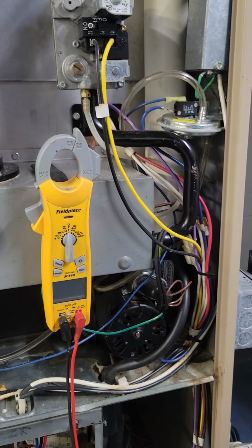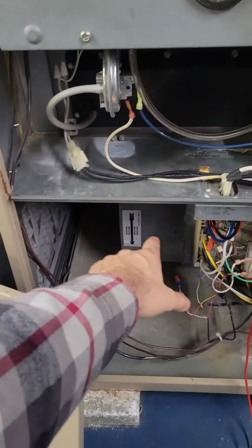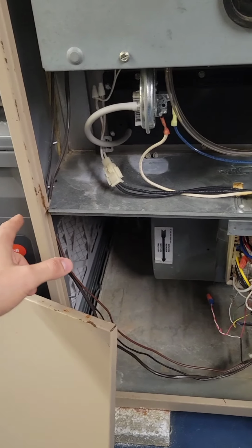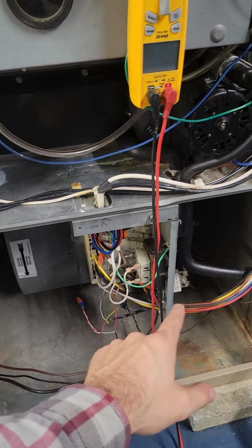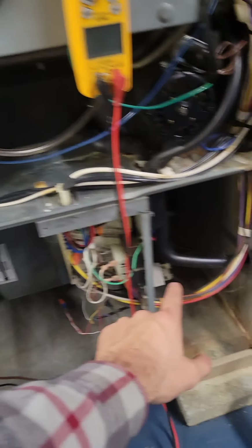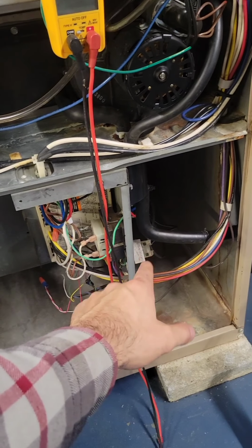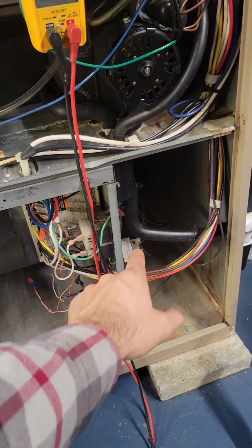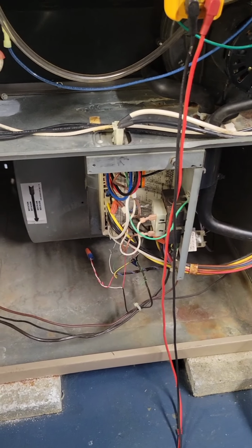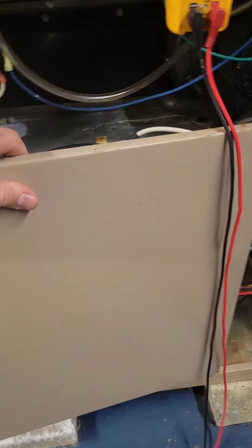So right now what we're gonna do is we're gonna put this cover back on. I already checked the blower motor. We changed the filter. We cleaned the condensate lines. We checked the transformer voltage. Check the other transformer voltage, even though the humidifier is not being used. They're using that for a humidifier. So that settles that. So we're gonna put this guy back on.